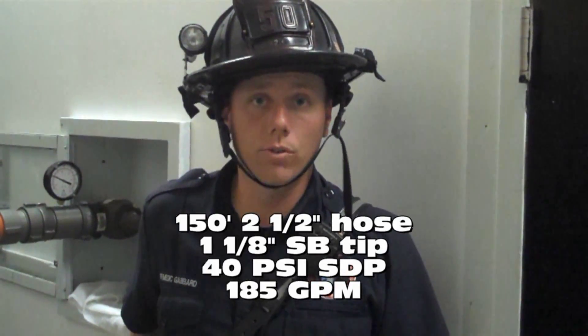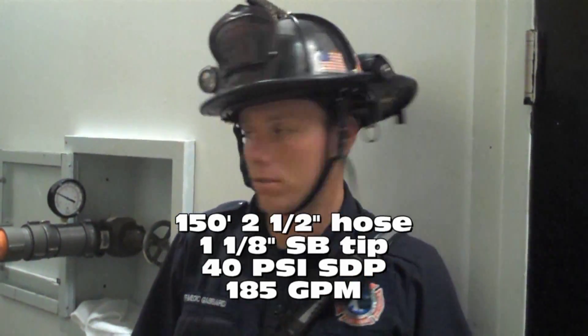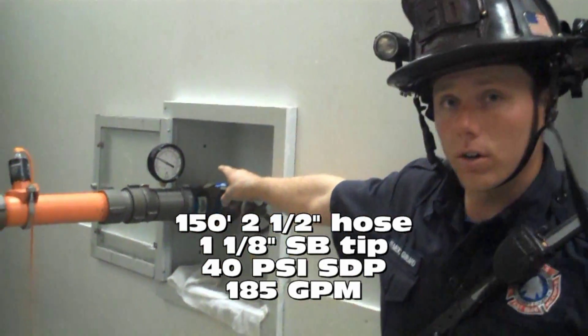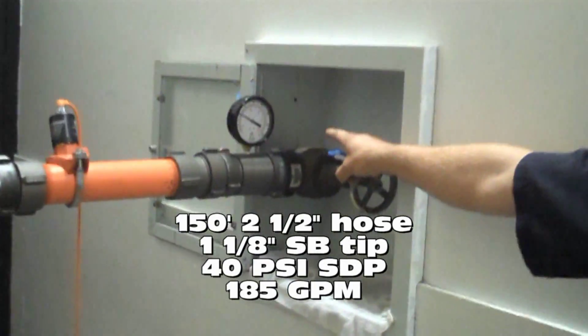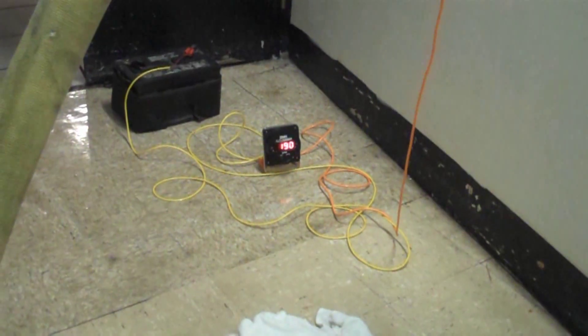We've got a 2.5-inch hose line with a 1 and 1/8 inch tip, three sections of 2.5-inch at 150 feet long. Our riser discharge pressure is right at 40 PSI. Our flow is 180 to 190 gallons a minute. That's with no additional pumping from the engine.